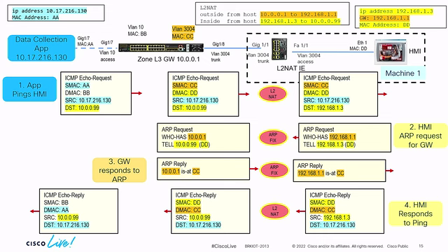So if you're talking about going back a couple of other slides where there was a controller in the machine that was in the same subnet. Again, you have to realize the machines have pre-built software and static MAC addresses, and all the components in there know their own IP address. So the HMI already knows that the IP address of the controller is .2 actually. So I didn't give the controller .1 on purpose, right? It's configured in the way the HMI knows the gateway as that controller.